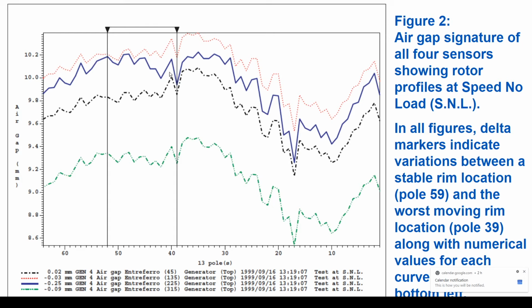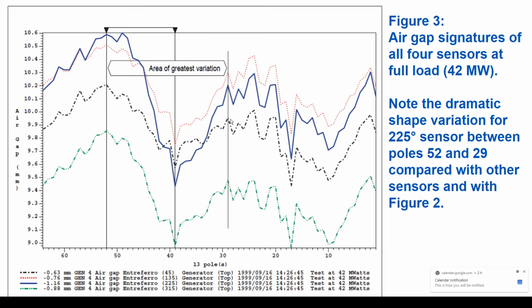So if you look at those results, they are somewhat parallel. Not exactly. If you have a trained eye, you'll see a difference. But this is the unit at no load. Basically, the traces were parallel. This is at 42 megawatts. I think anybody can see there's definitely an issue here. Okay. This sensor is not seeing the same profile in this location only as the other sensors. If you look at this section, they are all parallel, but this section is not.